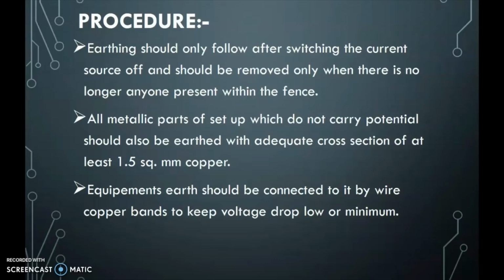Now the procedure. Earthing should only follow after switching the current source off, and should be removed only when there is no longer anyone present within the fence. All metallic parts of the setup which do not carry potential should also be earthed with an adequate cross section of at least 1.5 square millimeter copper. Equipment earth should be connected to it by wire or copper band to keep voltage drop low or minimum. Further portion will be presented by my friend.